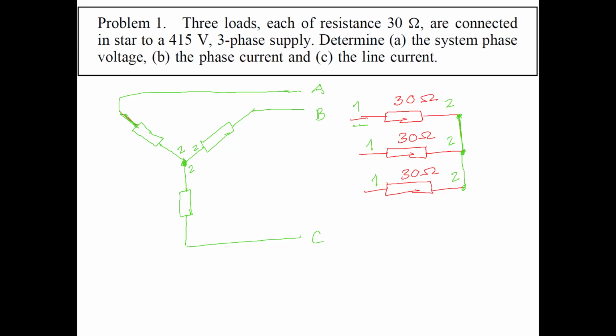So you are connecting between one phase and the neutral, and that gives you 230 volt. If you convert this 230 volt to line voltage, it becomes around 400. But 415 is a very standard value. So the line voltage at the low distribution line will be 415 volt. Okay, clear?